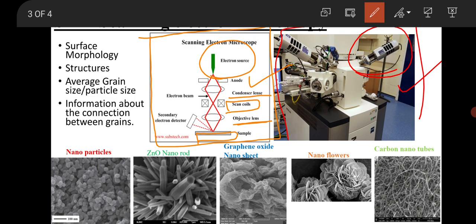Here is the scanning electron microscopy setup — this is the practical setup with the detectors. You keep your sample inside and measure or observe the morphology by scanning deeper and deeper. You can scan your sample at 10 micrometers, 1 micrometer, 100 nanometers, and even 1 nanometer. Depending upon the resolution of your instrument, you can scan your sample and go to the deeper level. If the morphology is clearly visible at 1 micrometer, you do not need to go to 100 nanometers. But if you need to observe nanoparticles or fine structures, you may need to scan down to 10 nanometers.